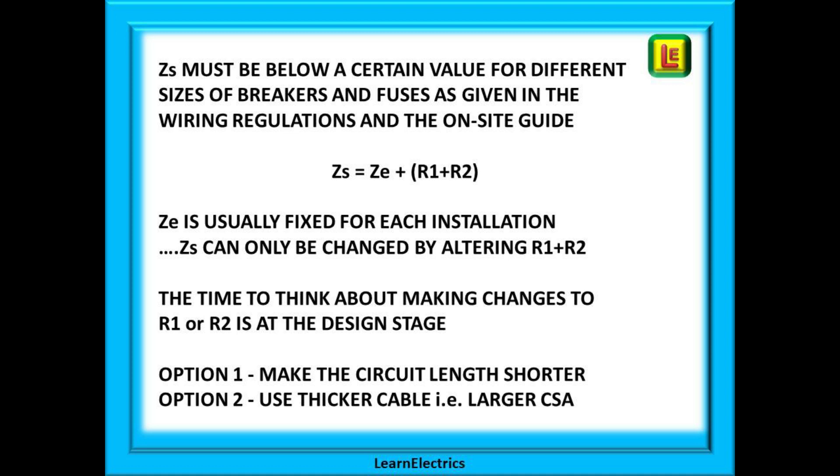And the time to think about making changes and altering R1 and R2 is at the design stage. Once the cables are in place it is so much more difficult to make the cables bigger or shorter. If ZS is too high and we need to reduce it to meet the wiring regulations, we have just three options.